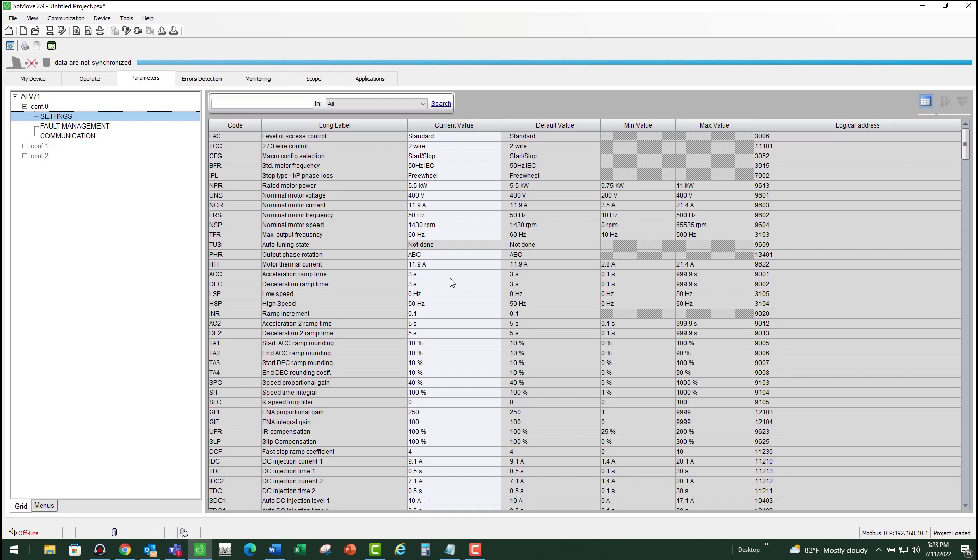The other reason could be regen energy from an overhauling load or high inertia load that can increase the bus voltage. So make sure you don't have such a condition that is causing the over-braking fault. You can also consider adding a dynamic braking resistor, which will basically absorb all that extra energy because of that overhauling load or the extra energy coming from the line side.